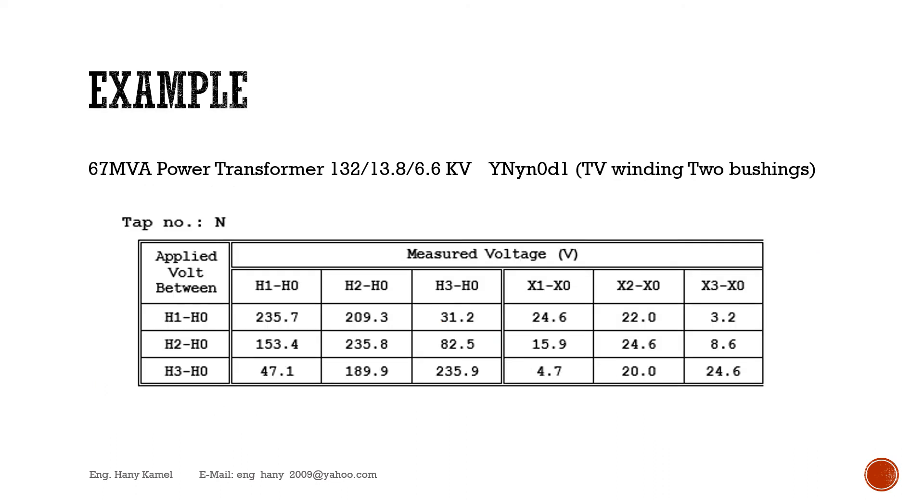On-site measurement example for 67 MVA power transformer, 132 over 13.8 over 6.6 KV. Vector group YN YN0 D1. Tertiary winding with 2 bushings from 1 delta corner.